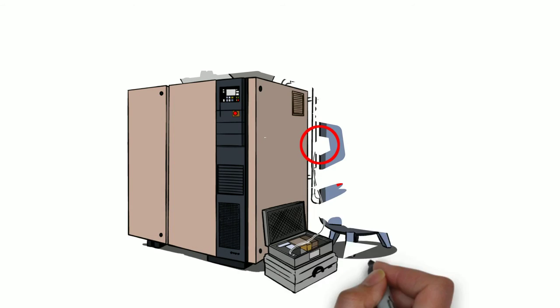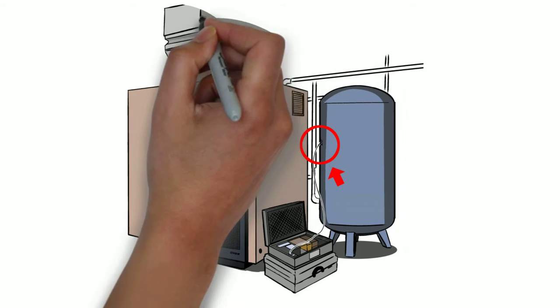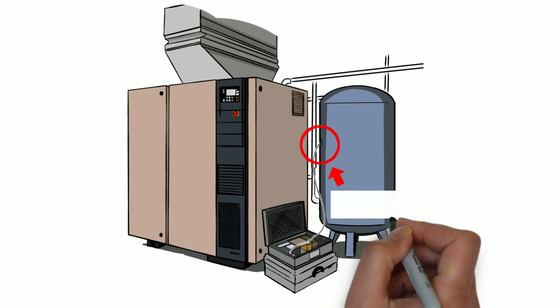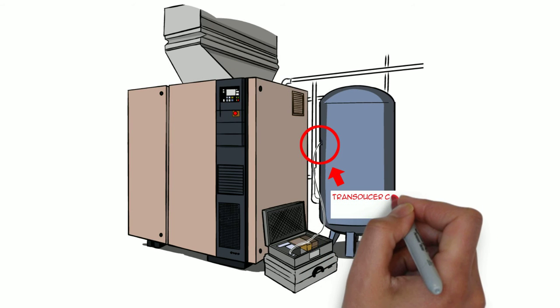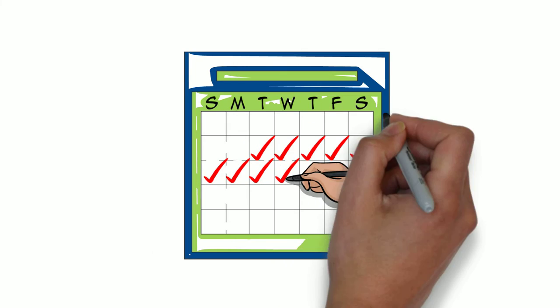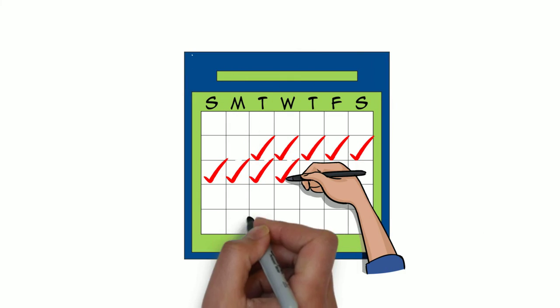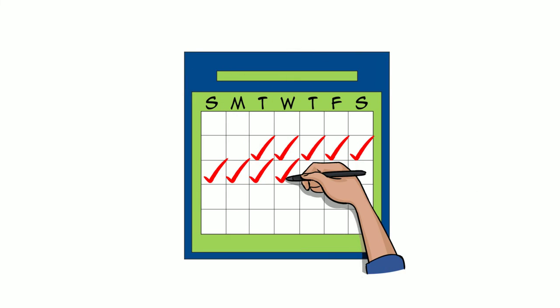On the storage tank, we install a pressure transducer to capture and monitor system pressure in PSIG. Data is collected for nine days to include two weekends and five days of production.